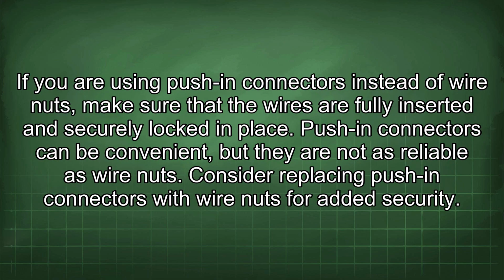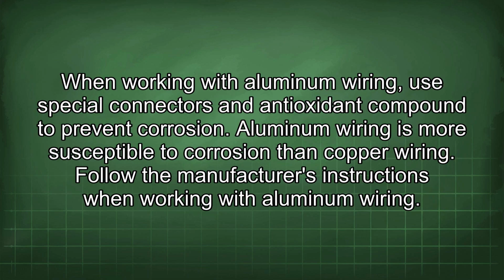If you are using push-in connectors instead of wire nuts, make sure that the wires are fully inserted and securely locked in place. Push-in connectors can be convenient, but they are not as reliable as wire nuts. Consider replacing push-in connectors with wire nuts for added security. When working with aluminum wiring, use special connectors and antioxidant compound to prevent corrosion. Aluminum wiring is more susceptible to corrosion than copper wiring. Follow the manufacturer's instructions when working with aluminum wiring.